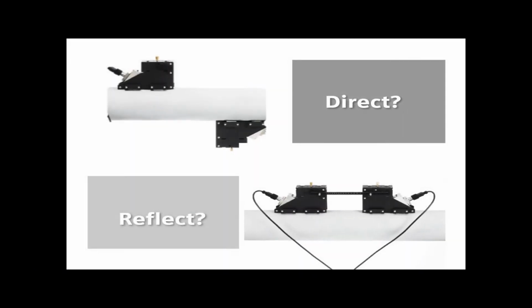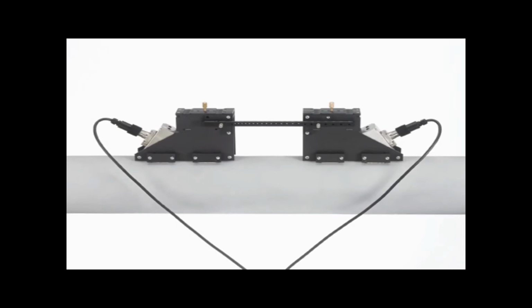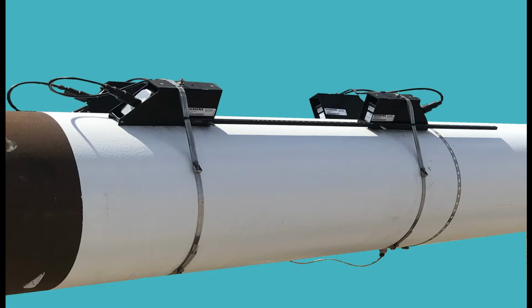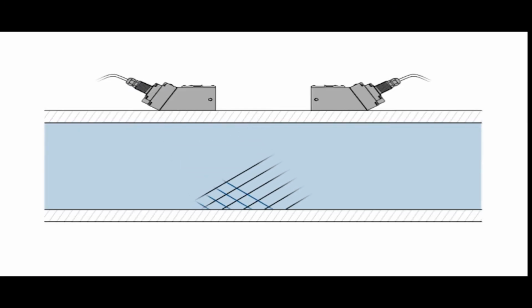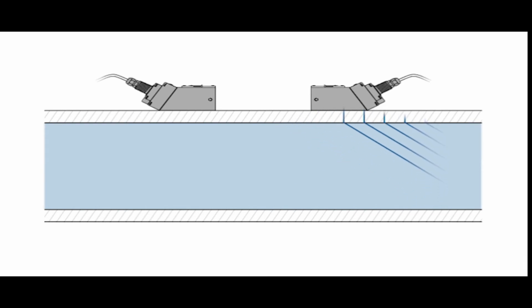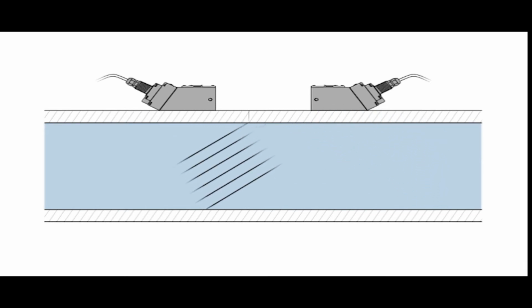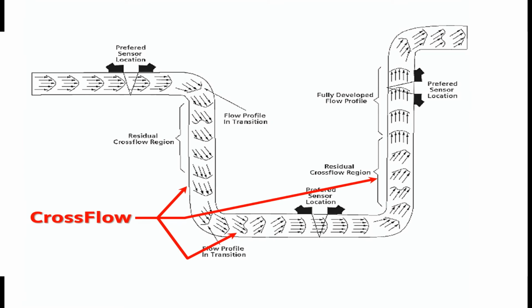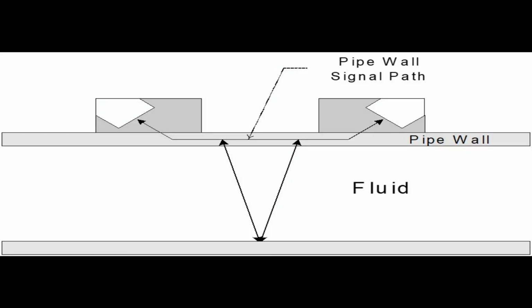So which mounting method is better? And why should you choose one over the other? The short answer is reflect mounting is preferred for several reasons. It's more precise, enabling use of a spacer bar with no need to measure the distance between the sensors. Secondly, it's more accurate because it provides better averaging of the flow profile and immunity to non-axial flow conditions, also known as crossflow. Third, it enables auto-zero functionality. And fourth, it's the easiest method of installation.